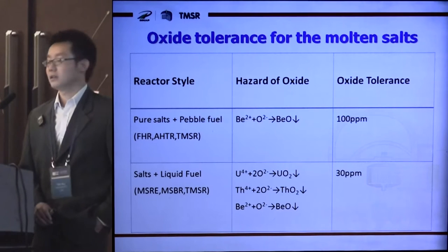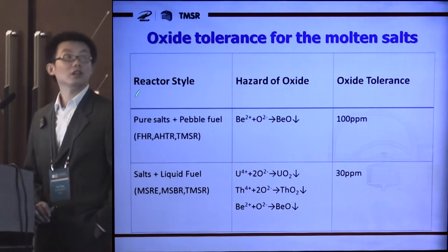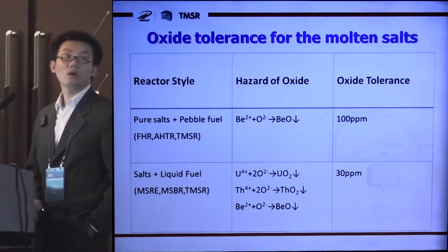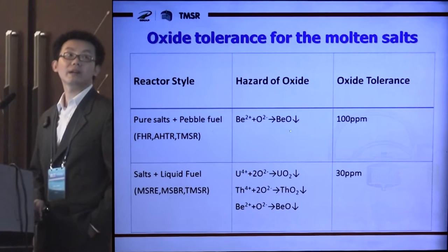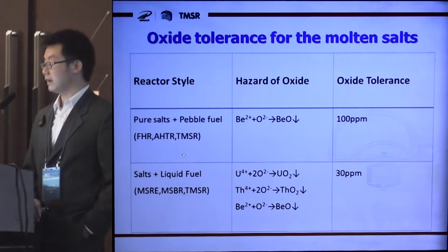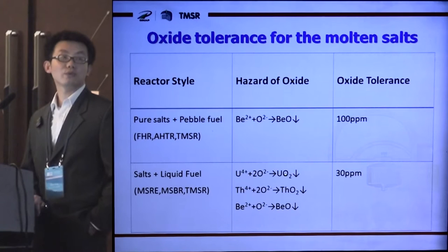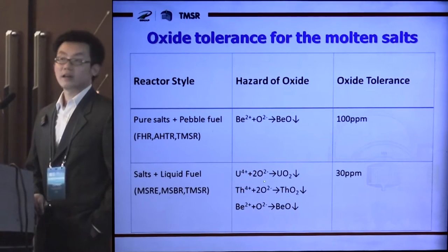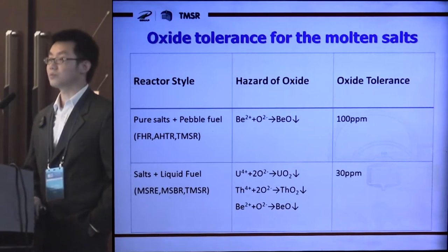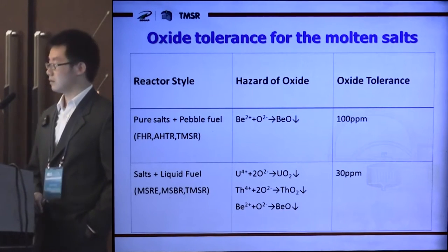Oxide impurity may not corrode the alloy directly, but it may cause other problems. In a reactor with pure salts as coolant, the oxide content in the molten salts should be controlled below 100 ppm to prevent the formation of beryllium oxide precipitation. In a reactor with liquid fuel salts as coolant, the oxide content should be controlled more strictly — below 30 ppm according to MSRE suggestions — because the solubility of uranium and thorium oxide in molten salts is much lower than that of beryllium oxide. This is a challenge for us.